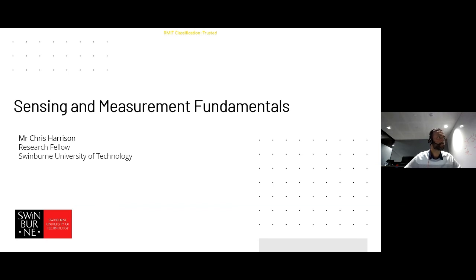test that? So in terms of that, there's two things going on, I suppose. One, your system probably will have a bunch of thermocouples in it, which are acting as thermocouples, right? You have deliberately selected them to measure the temperature at some point in your system. When I was talking about the thermoelectric effect, it's usually the introduction of unintentional thermocouples. So if you have a very, very small signal, and along the cabling that's carrying that signal you have a junction between dissimilar metals, it can inject a very small voltage into that signal. And that can cause all sorts of confusion and chaos.